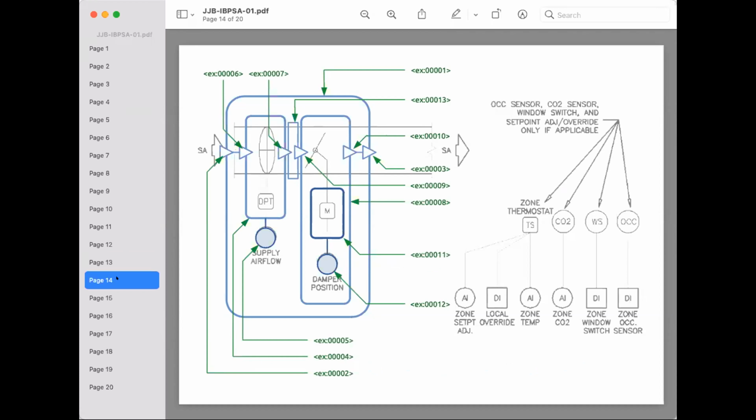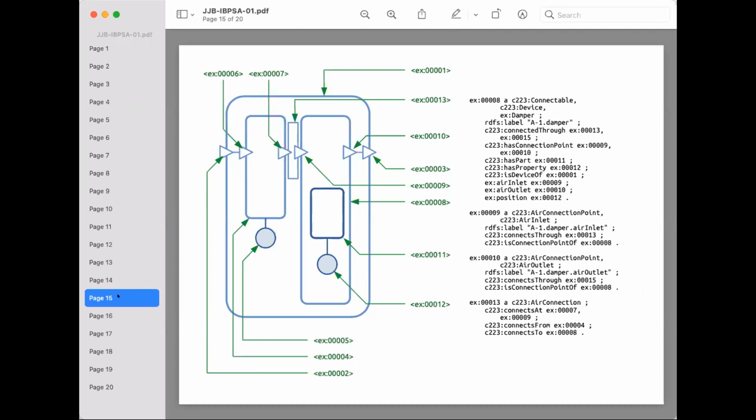We give each one of those an individual component, a unique identifier within the graph, and then we can build a graph of these relationships between elements. So this RDF graph is used in our case to precisely place the property of a system, such as the temperature leaving a unit, unambiguously in the topology of the system itself to assist with classification of what that particular property is. So one of the challenges in our industry is that a lot of people call the same thing by different terms.